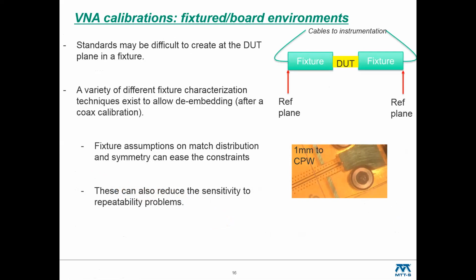Moving to a slightly more practical world where you have a test fixture where you have to connect your device. This can present a bit more of a challenge, since at this DUT plane in the middle, it may not be a terribly high repeatability range if it's spring points or some kind of pin contact. But still, you want to move the reference planes into that inner plane. And there are a number of ways of doing that, and that's been a significant development in the last few years: how to characterize these fixtures in a convenient way that's sufficiently accurate for measuring things like fixtures that are up to 110 gigahertz in this little shot here.